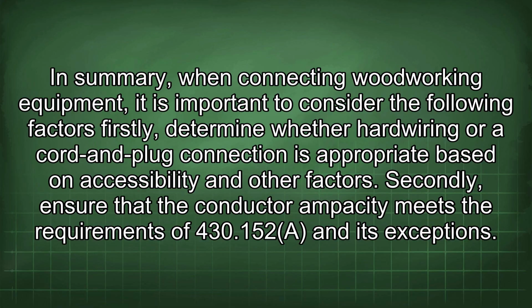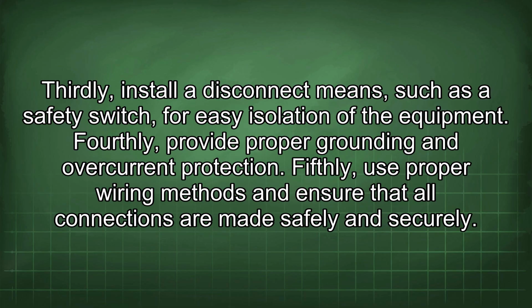Firstly, determine whether hardwiring or a cord and plug connection is appropriate based on accessibility and other factors. Secondly, ensure that the conductor ampacity meets the requirements of 430.152 and its exceptions. Thirdly, install a disconnect means, such as a safety switch, for easy isolation of the equipment. Fourthly, provide proper grounding and overcurrent protection. Fifthly, use proper wiring methods and ensure that all connections are made safely and securely.